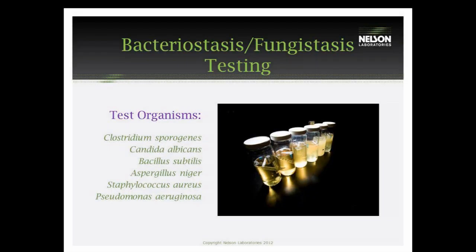After we get these results, the same samples will be transferred for bacteriostasis/fungistasis testing. We will inoculate each test vial with the specific test organism listed. These need to demonstrate growth. What this test proves is that there is nothing in the device that will inhibit the growth of organisms and give us a false negative result in our product sterility testing. This series of BF testing is only required one time on the device unless there are any manufacturing or product changes. That data can support product sterility testing from then on out.